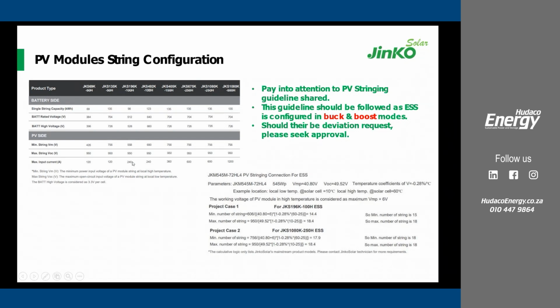We've also given 558 to 950 for the 98 kilowatt hour battery strengths. Pay attention to this, because if you have a lower PV voltage compared to the battery voltage in the buck mode, you'll find that charging is actually limited and the batteries will stop charging. The PV voltage in buck mode must always be more than the battery voltage by at least 50 volts.